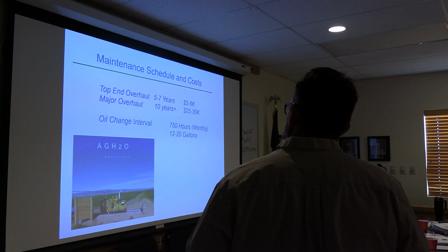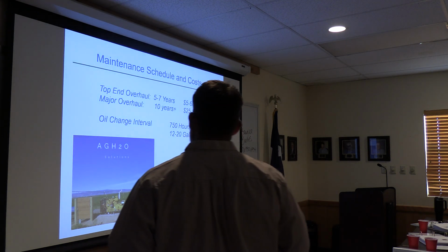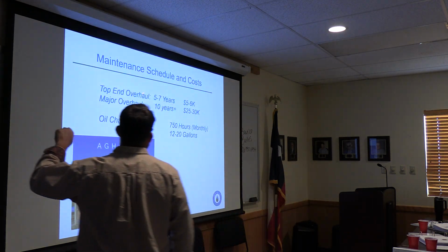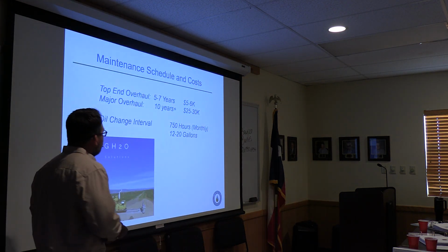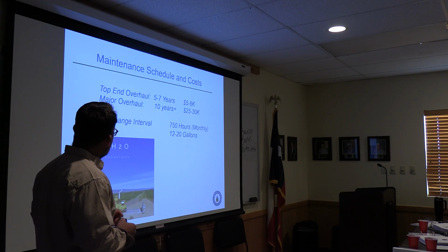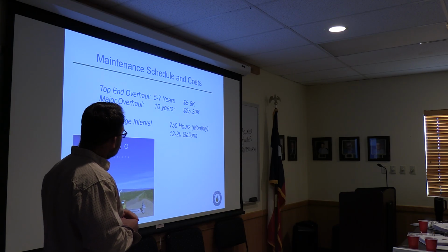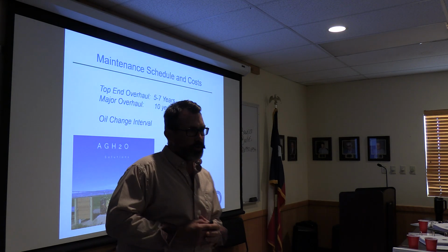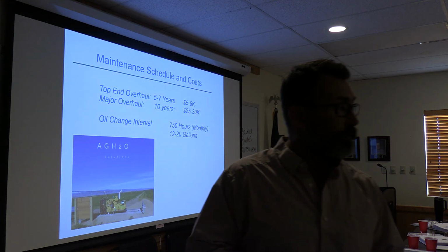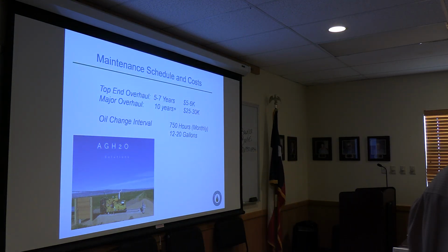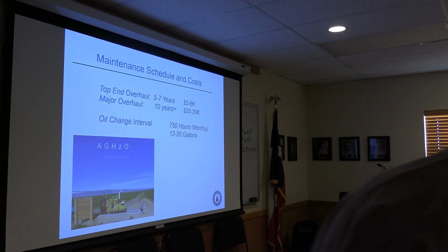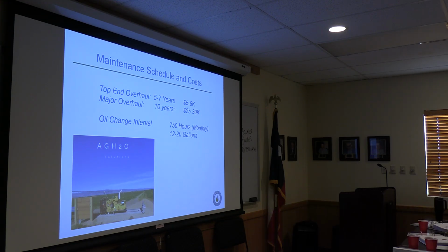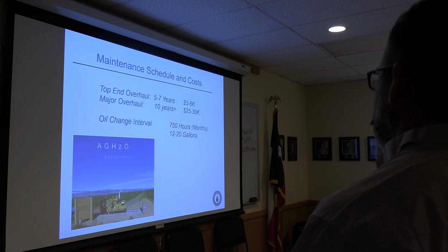So maintenance schedule and cost to consider. Top end overhaul on a gen set, probably 5 to 7 years. This is an industrial motor at 5,000 to 6,000, maybe a little bit more per major overhaul, 10 years plus. A lot of our industrial motors, if we take good care of them, they're going to last a long time. The generators will last a long time as well. So it'd probably be considered some sort of CapEx investment if you're doing this, depending on how you want it to line it out. Your major overhaul term is way out there.